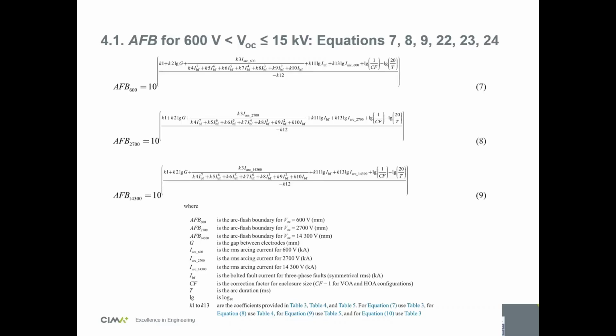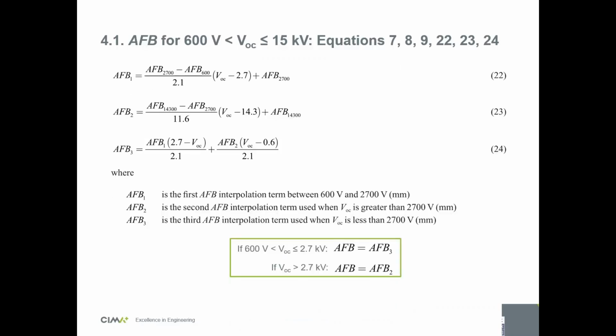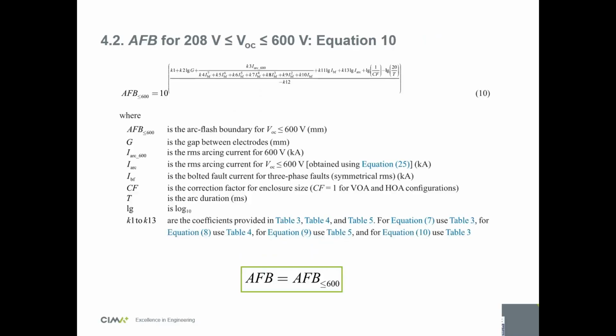So this is the equation for the arc flash boundary. So it's 10 to the power of this big fraction. You need to calculate three interpolations, three arc flash boundaries: at 600, at 2700, at 14.3 kV, with your arcing currents, your gap distance, your fault current, your enclosure size, your arc duration, and then you need to interpolate again, find AFB1, AFB2, AFB3, and then your final arc flash boundary. If you're below 2.7 kV, it's AFB3, and if you're above 2.7 kV, it's AFB2. When you're below or equal 600 volt, the equation is simpler. You don't need to calculate 3, you only need to calculate 1. So it's this equation here, and your final arc flash boundary is directly this value.